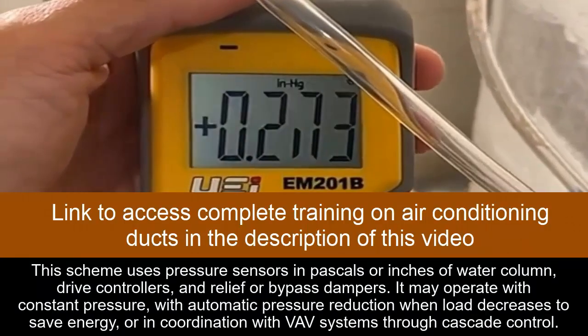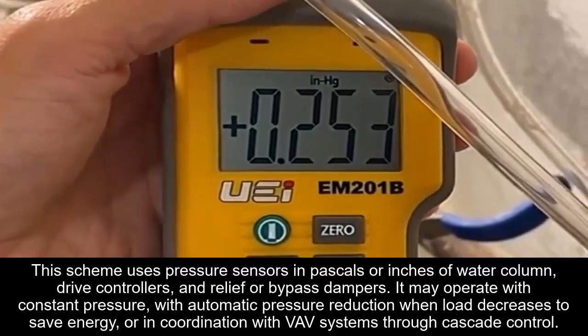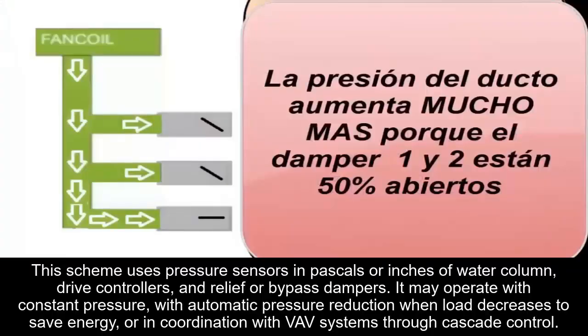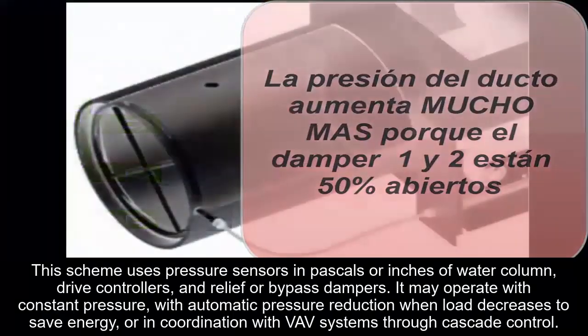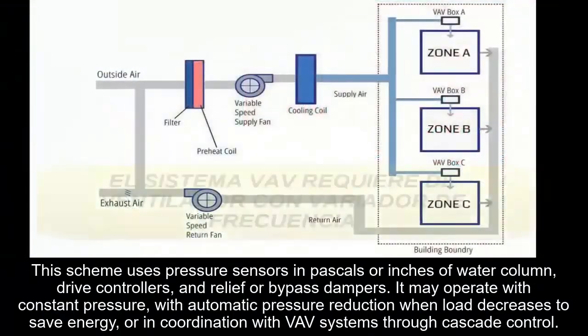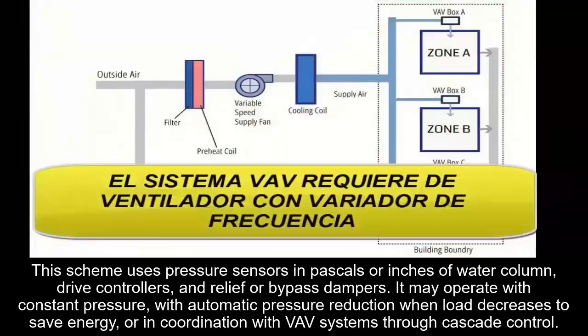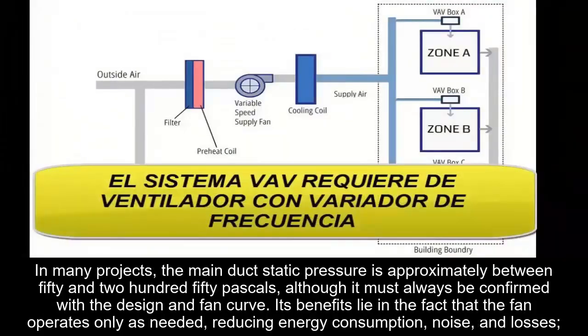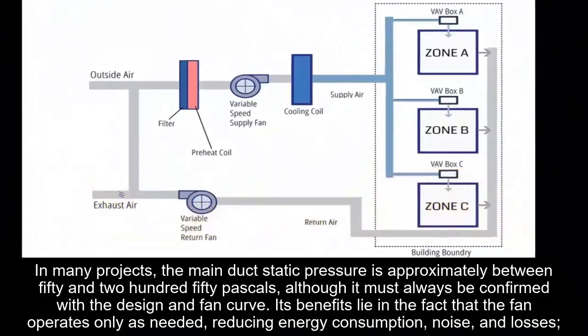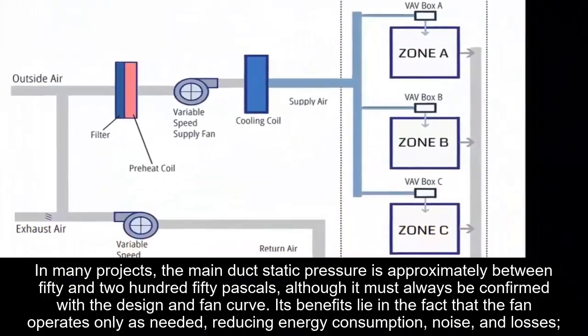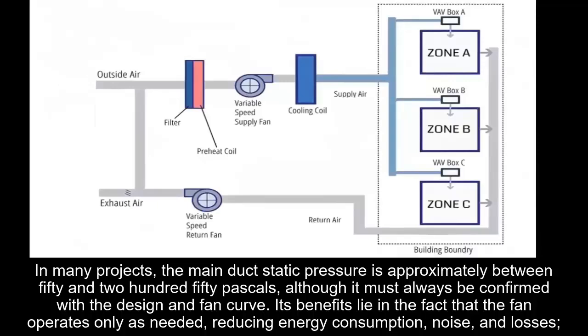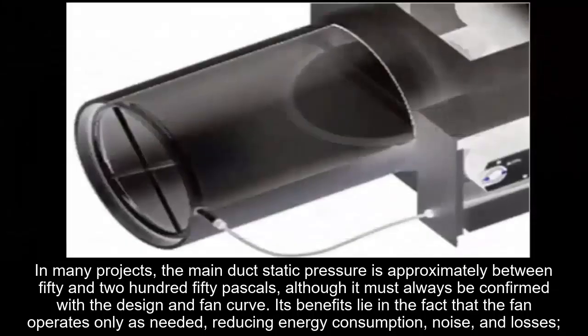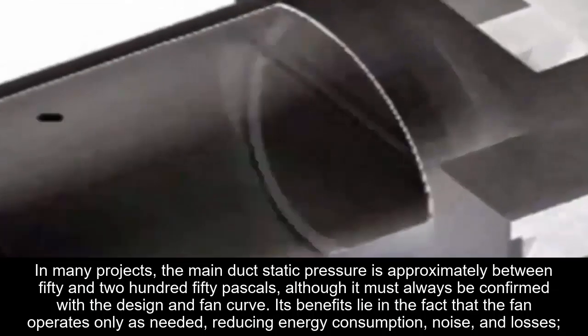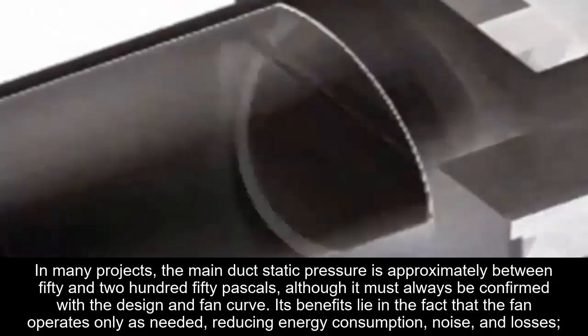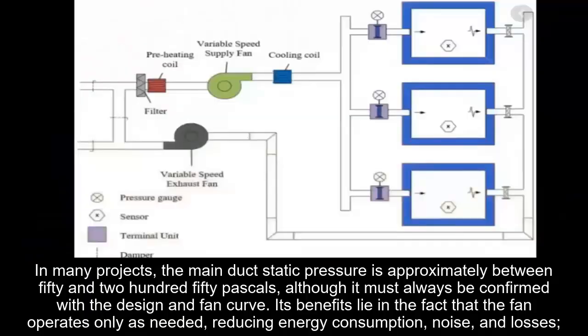This scheme uses pressure sensors in pascals or inches of water column, drive controllers, and relief or bypass dampers. It may operate with constant pressure, with automatic pressure reduction when load decreases to save energy, or in coordination with VAV systems through cascade control. In many projects, the main duct static pressure is approximately between 50 and 250 pascals, although it must always be confirmed with the design and fan curve.